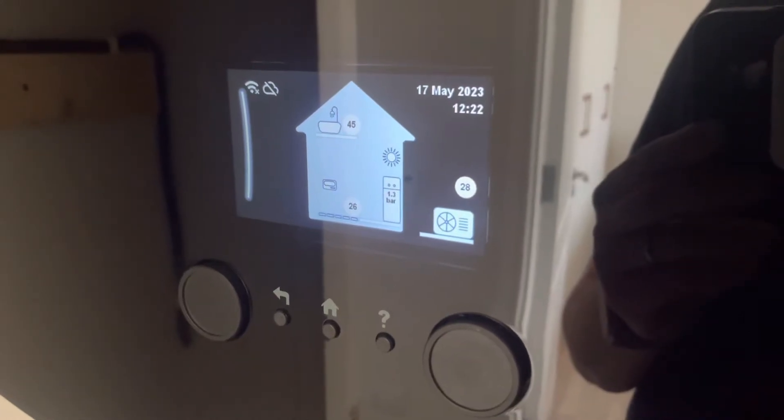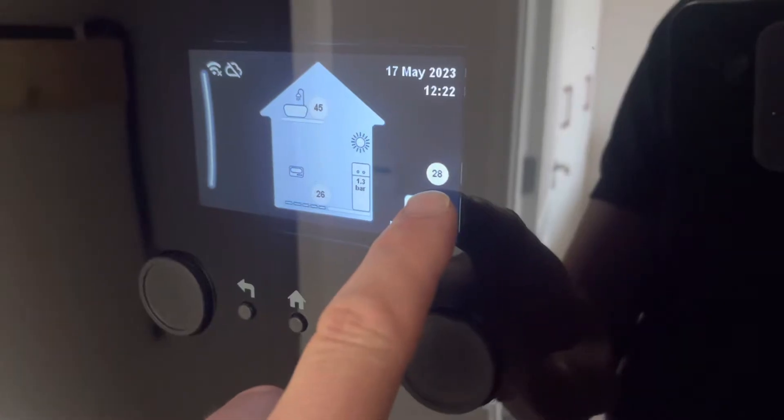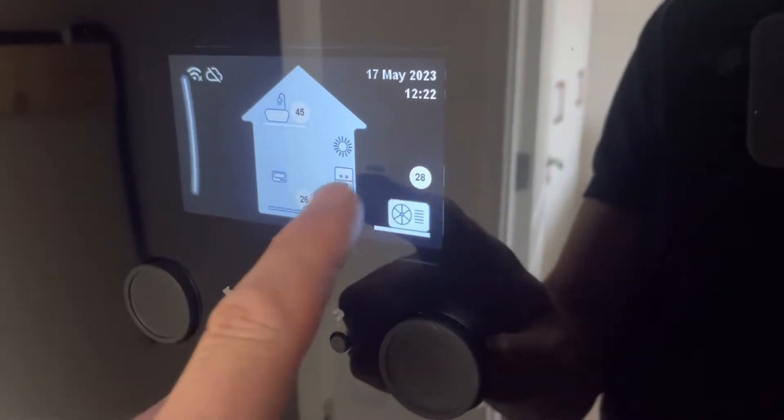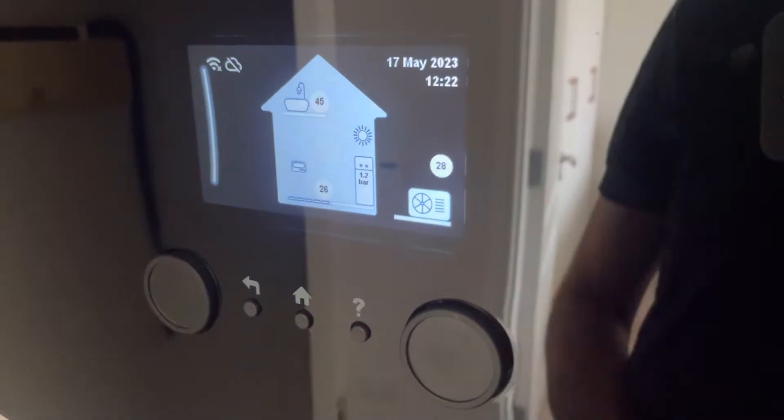This is a Daikin Altherma 3. Outside temperature — because the sun is shining on the sensor today — is 28 degrees. Target flow temperature is 26. Pressure in the system is 1.2 bar. The hot water temperature is currently 45.